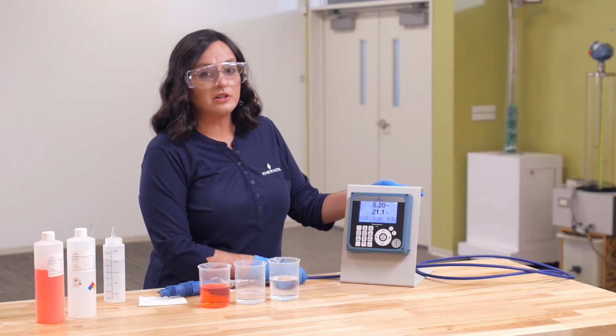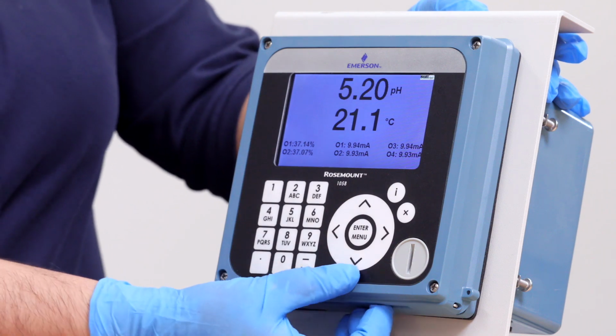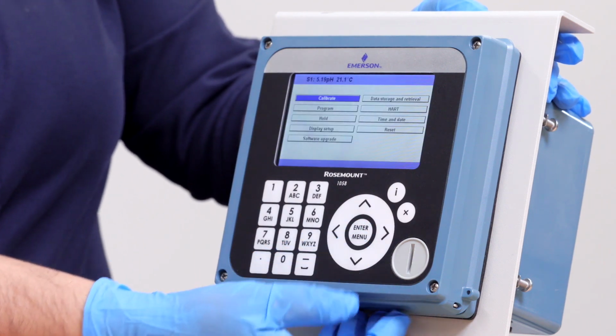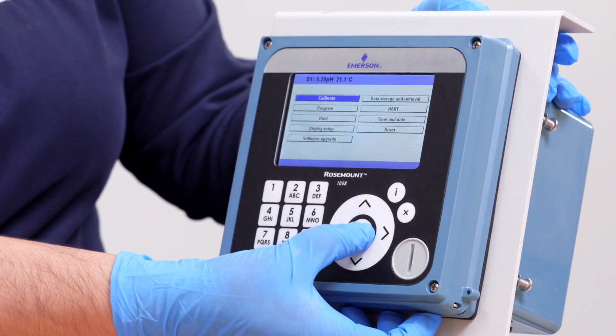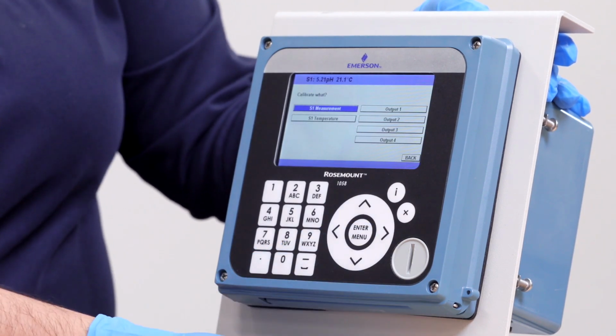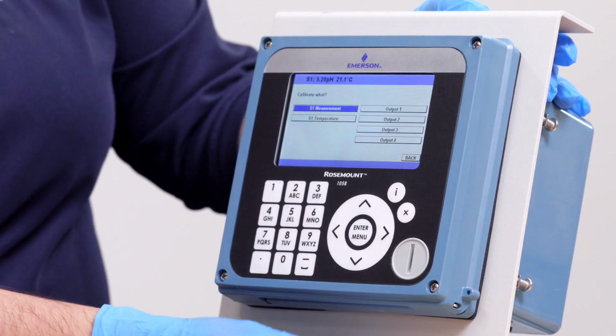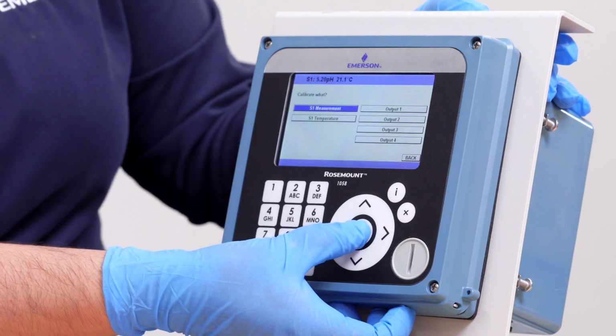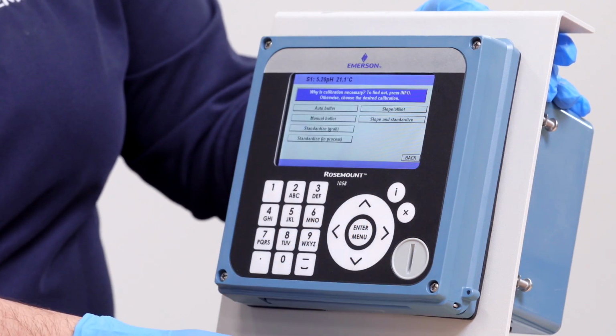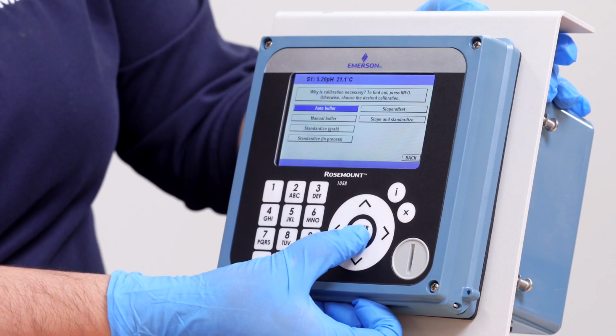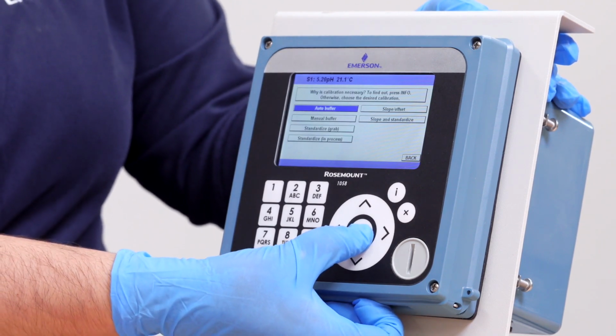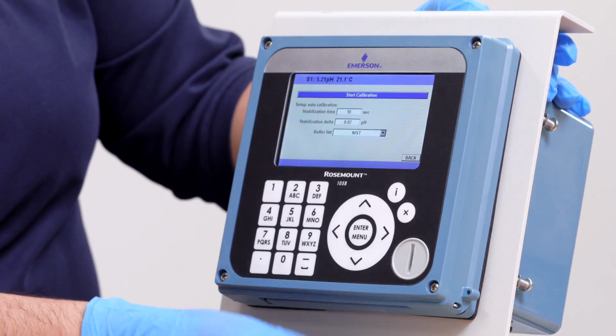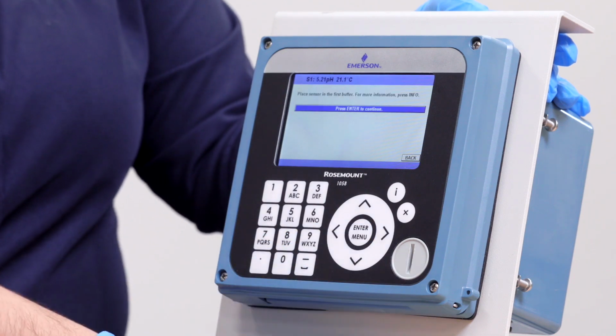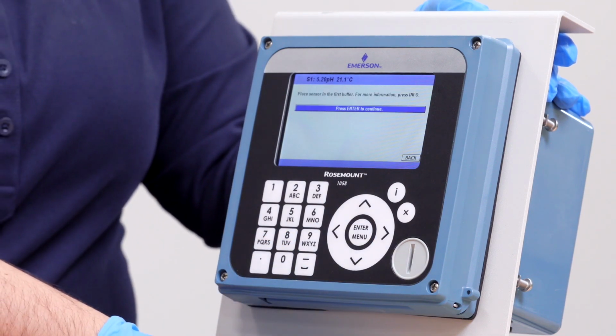To access the auto calibration menu, first press the Enter menu button on the transmitter. Then select Calibrate. Next, select the sensor you are calibrating, and in this case, S1 measurement. Then press the down arrow and select Auto Buffer. Hit Enter. And finally, start calibration. Now you can follow the directions on the transmitter screen.